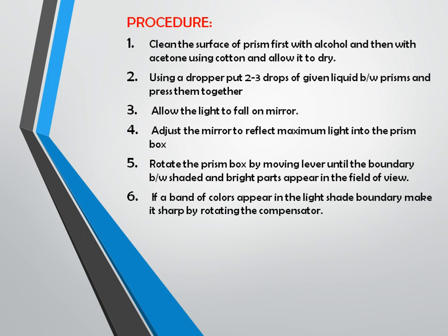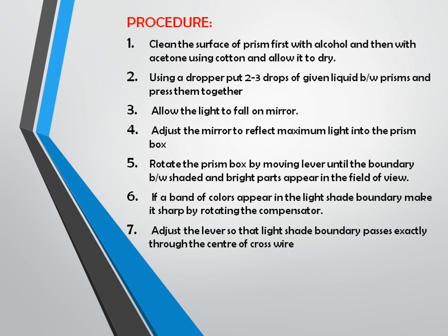After cleaning with alcohol and acetone and placing the sample drops between the two prisms, adjust the mirror for maximum light reflection, then rotate the prism and set the eyepiece view so that half is dark and half is light. For that purpose, move the rotating compensator. Then adjust the lever so that the light-dark boundary passes exactly through the center of the crosshair. Read the refractive index directly on the scale from the second eyepiece.